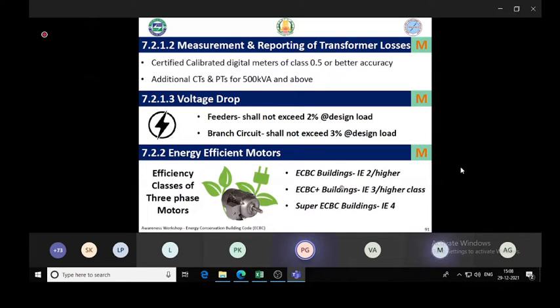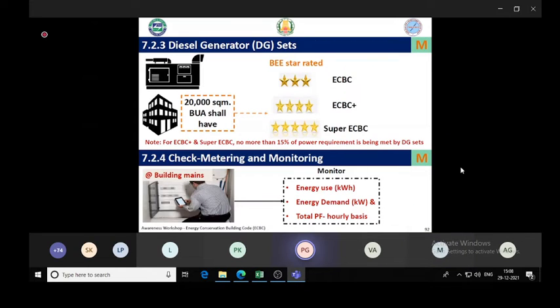Motors: the minimum efficiency of motor should be IE2 or higher. Nowadays IE2 motors are very common, so that's pretty easy, but this has to be specified and ensured. So any motor, whether it is a pump or any HVAC equipment, should comply with IE2 efficiency. And for ECBC Plus and Super ECBC, IE3 and IE4. DG sets: again, the code specifies that if the building is more than 20,000 square meters, then at least a 3-star rated DG should be used.